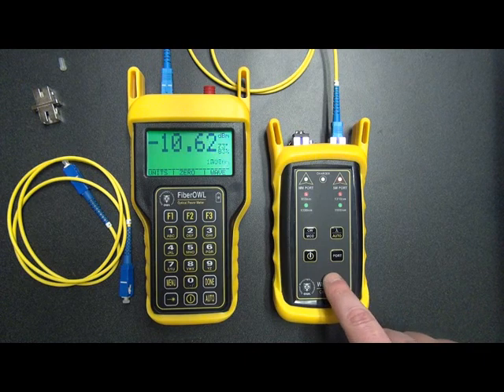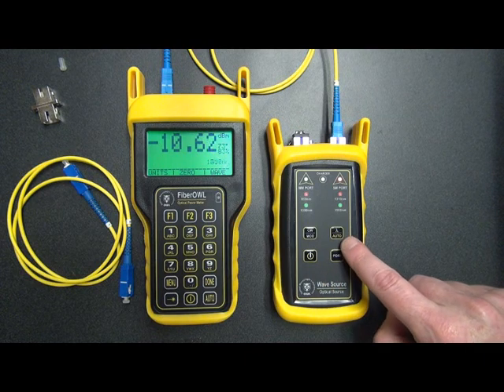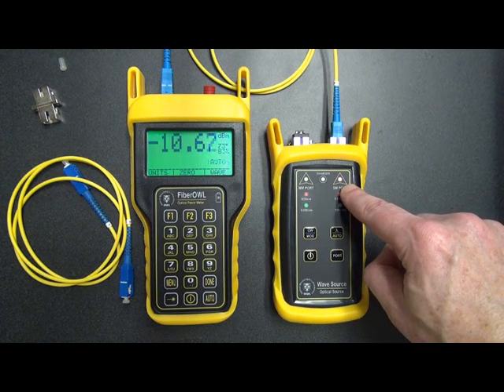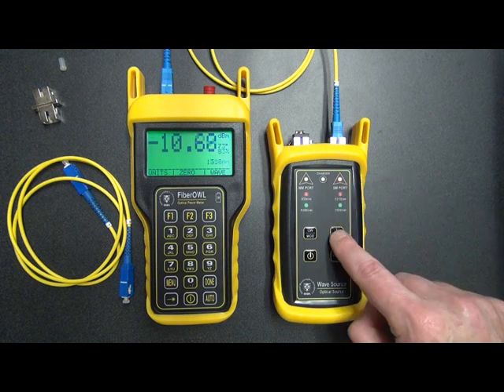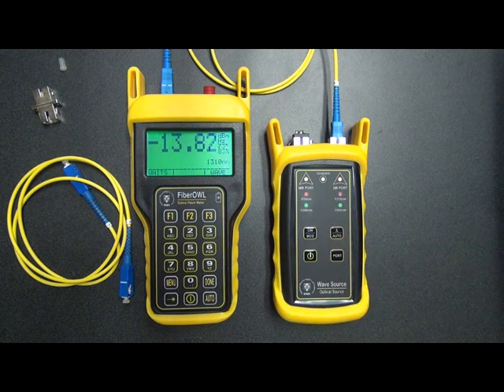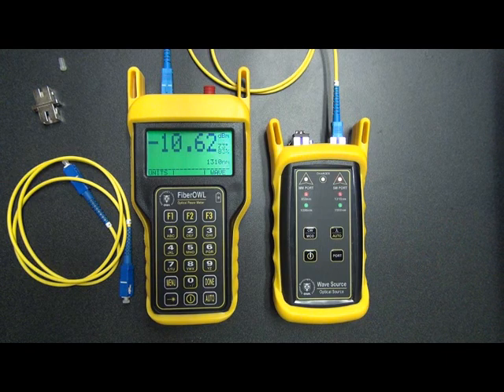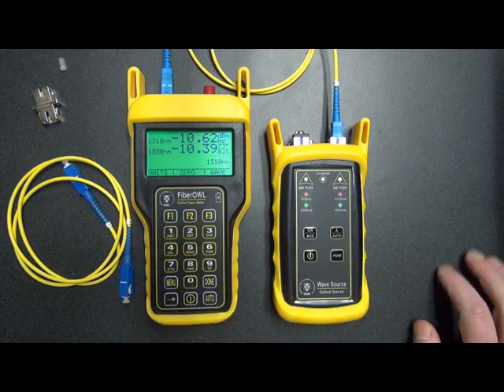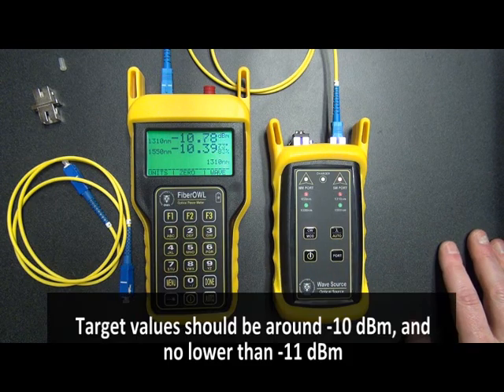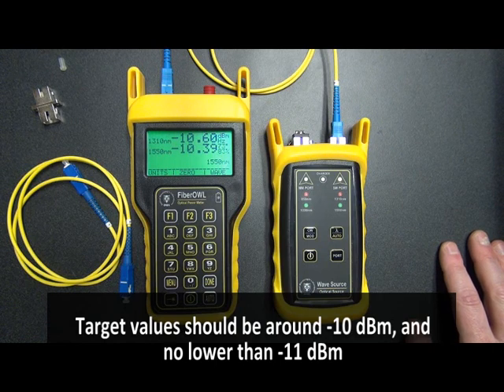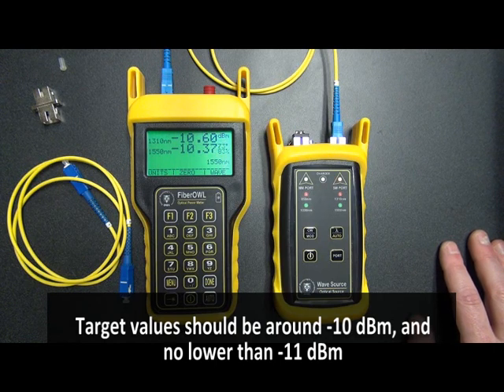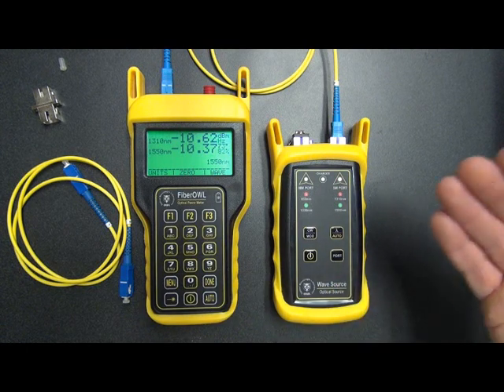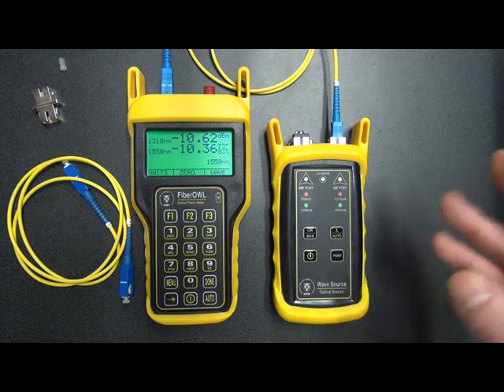So we need to set the wave source into auto mode as well. This is done by pressing and holding the auto button, watching the indicator LED, and the second it starts flashing, we remove our finger. We'll watch it for a few seconds and it should begin switching between red and green. We should also see a reading on the screen here. We'll see that 1310 has a reading of minus 10.6, 1550 is minus 10.37. So these are both acceptable power levels. We're not below minus 11, we're still around minus 10.